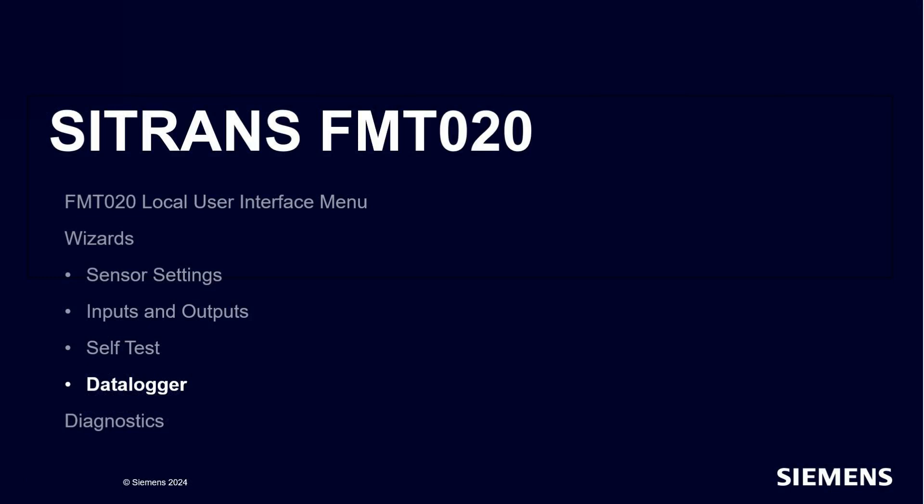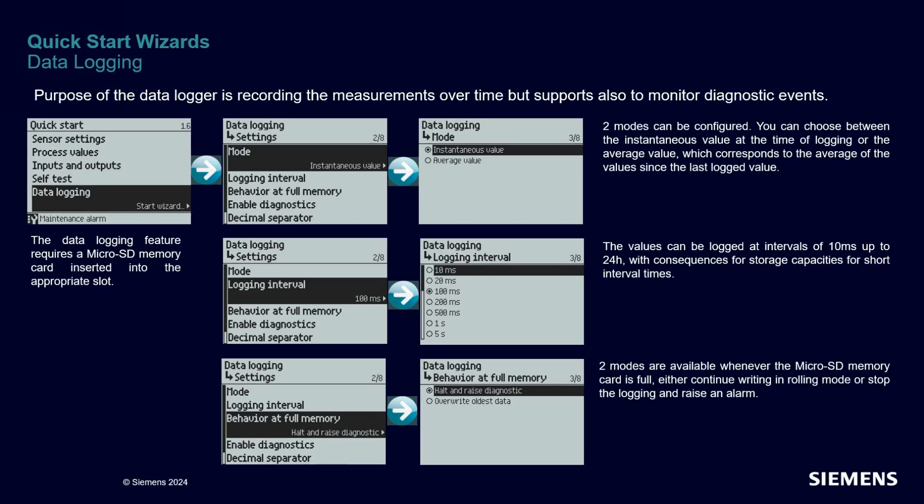The last wizard for this webinar is the data logger. In order to save your log file, the FMT-020 needs a micro SD card to be installed. If you intend to use the data logger, don't forget to purchase the SD card as an option. We provide an option for an industrial micro SD card to fulfill harsh testing conditions, but if your environment is more friendly, you can use any commercial micro SD card, as long as the capacity is 32 gigabytes or less.